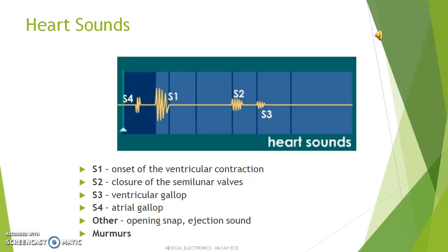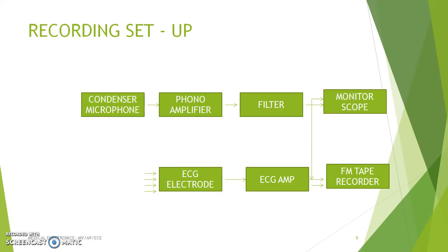This is the recording setup of the PCG waveform. The recording setup consists of the following components: a condenser microphone, a phono amplifier, a filter, a monitor scope, an ECG electrode, an ECG amplifier, and finally a tape recorder. Initially the heart sounds are converted into electrical signals by means of a microphone pressed against the chest wall by a strip. The pickup is successively located at different areas. The electrical signals from the microphone are amplified by a pre-amplifier, followed by a filter and recorder. Electrodes are also placed on the limbs to pick up the electrical activity of the heart, and these signals are amplified and recorded. The recorded ECG is used as a reference for the PCG.